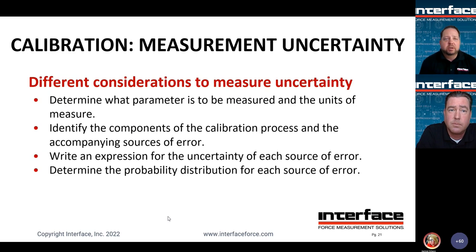So it starts with obviously understanding what's the parameter to be measured, what are the units of measure. Then you need to go through the different components of the calibration process. And this is more so for a cal GUM, if you will, or cal uncertainty. And then what are the accompanying sources of error for those components? From that, you need to create an expression for the uncertainty for each source, and then assign a probability distribution for each source as well.